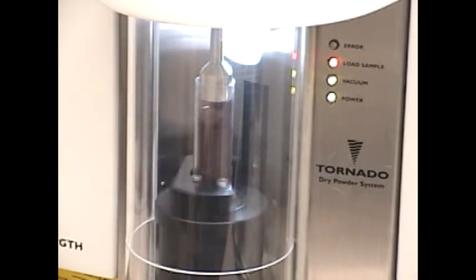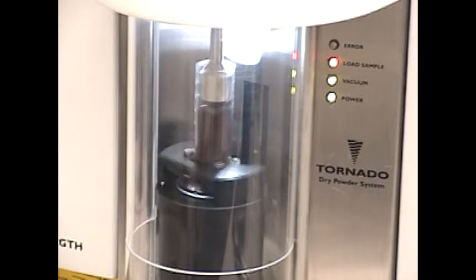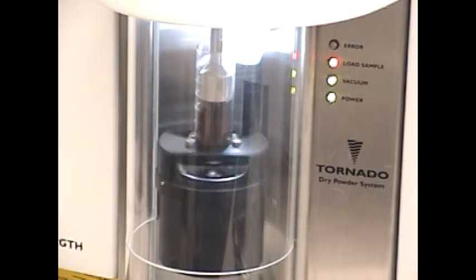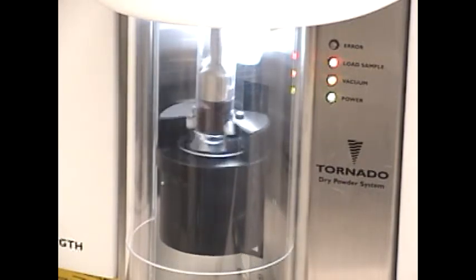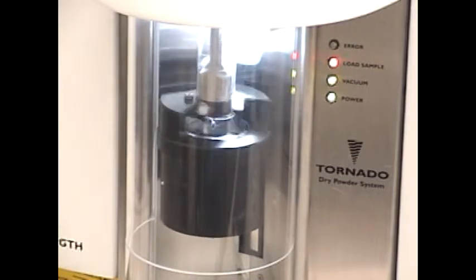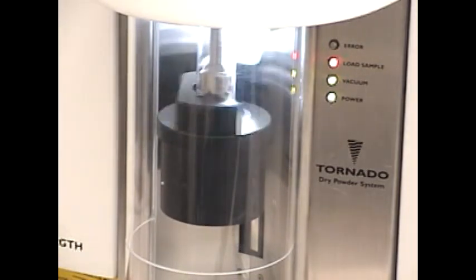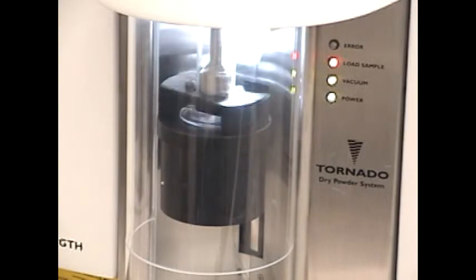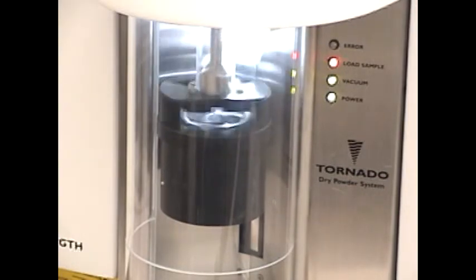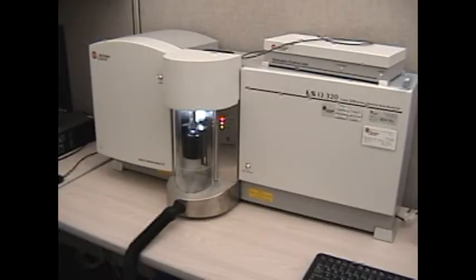Pressurized air uses shear forces to disperse agglomerate with a vortex instead of acceleration in a straight line. The combination of vertical grooves along the suction probe and the vortices created at the tip of the probe produces high shear forces that disperse the powder. This whole process happens within a matter of minutes to determine the material size. Let's take a look at the results.